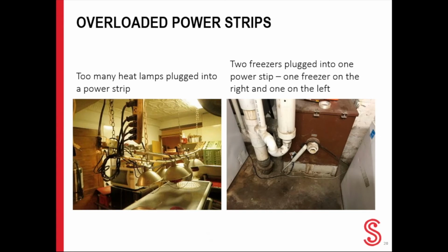Overloaded power strips. Now, if you look at this power strip on the left in the kitchen, you're looking at 1, 2, 3, 4, my gosh, 5 outlets plugged into it. This is an extremely overloaded power strip. Can you overload a power outlet? A power point overload occurs when you exceed the maximum amperage of the electrical circuit you are using. This can be caused by plugging too many appliances into one power point or running appliances that draw high amps at the same time. The result of an overload can be a short circuit and quite possibly a fire. This is also a problem in offices when staff plug too many office machines into one power strip. This can result in a fire.